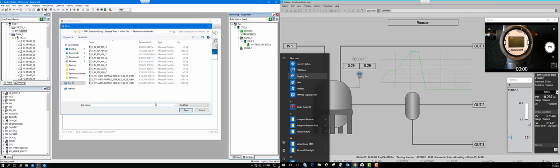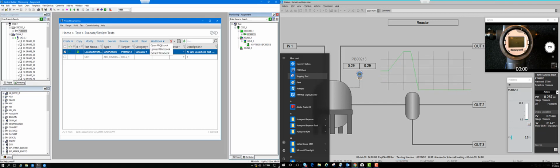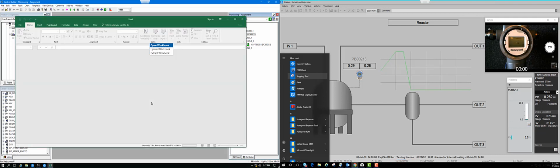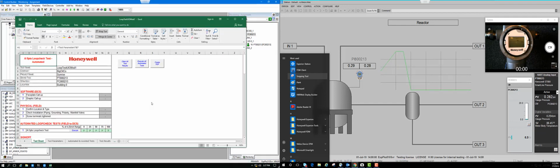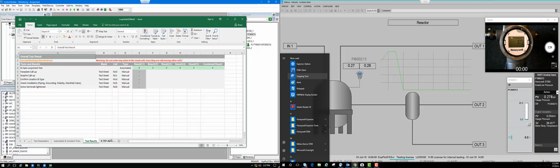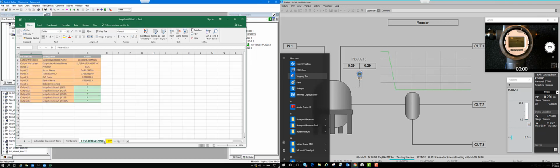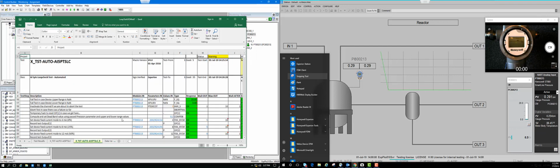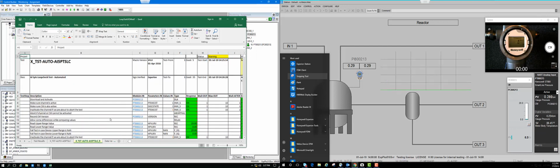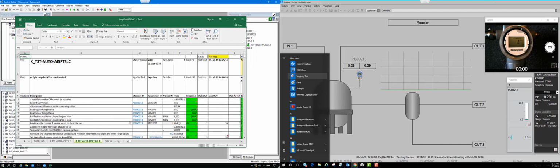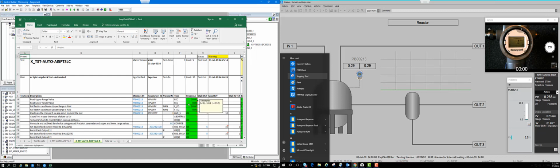Let's upload the workbook. Ooh, that's not it. Open the workbook there. And let's see what we have. Okay. So test results, passed. Everything has passed here, 0, 25, 50, 75, 100, and here's the actual test. Okay, so here's the sequence of events that has to happen for the test to work successfully. Here is where it sends the instruction to view the upper and lower range value, which in my case is 0 to 20 pounds.